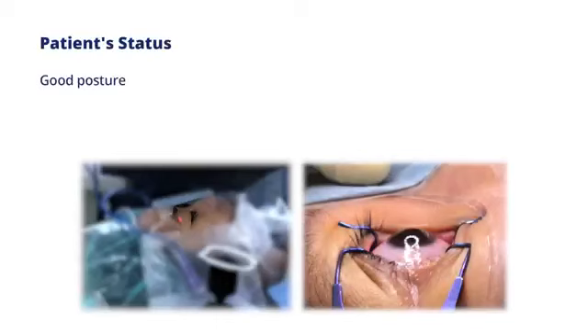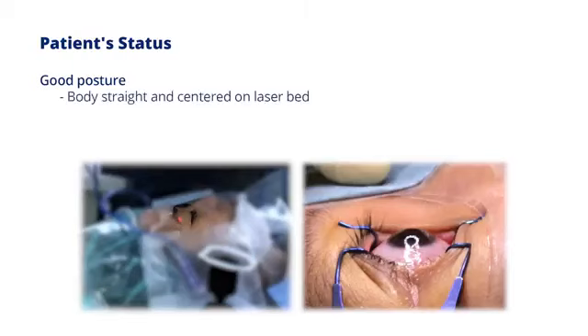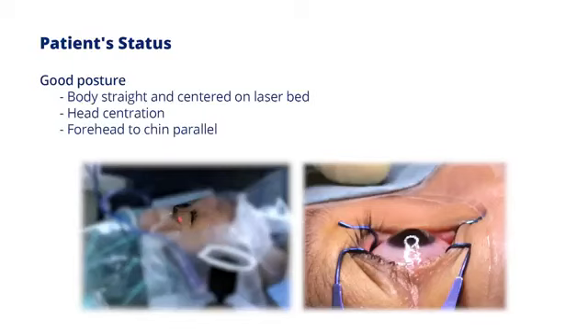Good posture of patient status relies on the four following positions. Body position should be kept straight and centered on the laser bed. Head position kept in the center of the back pillow in routine, but tilted to one side if prominent nose hinders the path of PI docking. Forehead to chin kept parallel level, but chin up for prominent forehead or chin down for prominent cheek.